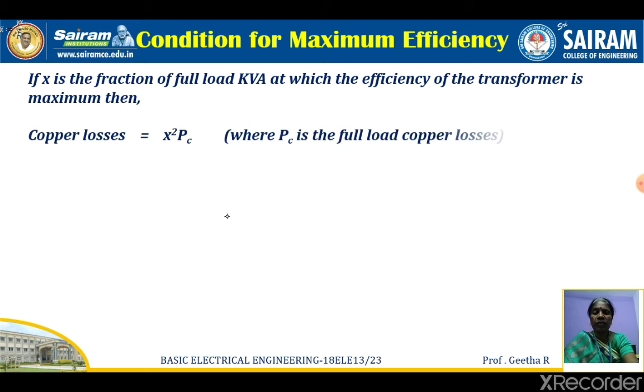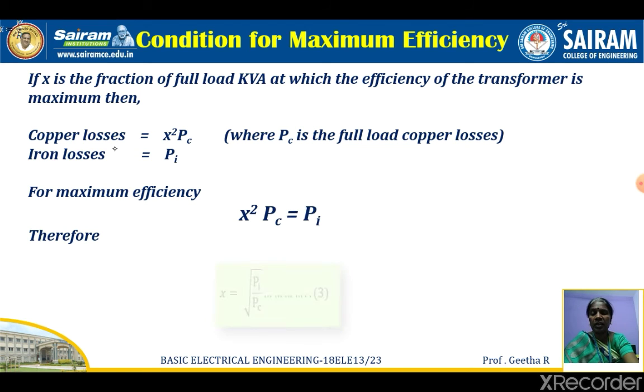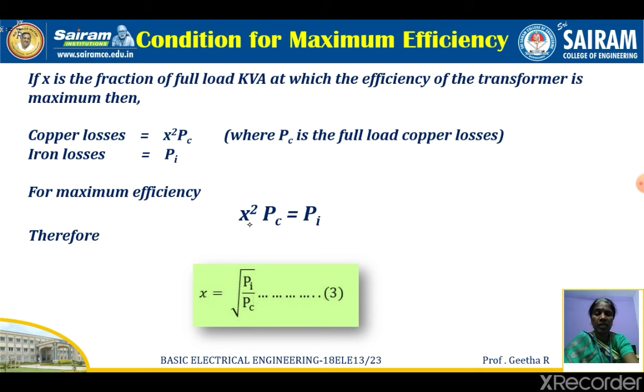If X is the fraction of full load kVA at which the efficiency of the transformer is maximum, then you can write copper loss is equal to X squared Pc. It is the fraction of full load kVA. Then iron loss is written as Pi. So since iron loss is equal to the copper loss, that is the condition for the maximum efficiency, you can equate these two, that is X squared Pc is equal to Pi. Therefore X is the square root of Pi by Pc.